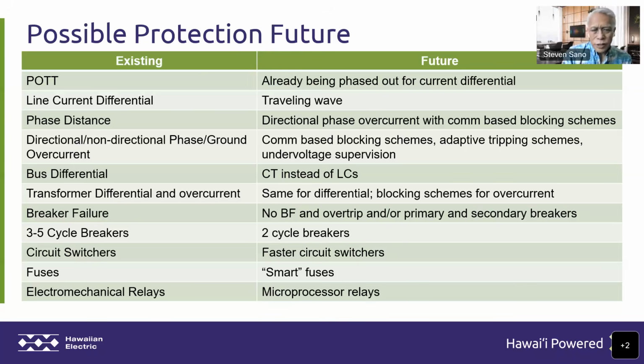Bus differential, again, it's those linear couplers, and that's just us. Transformer differential and overcurrent type protection. Again, same sort of thing for the differential protection should work. Some issues with the overcurrent and directional, so maybe some blocking schemes for that.